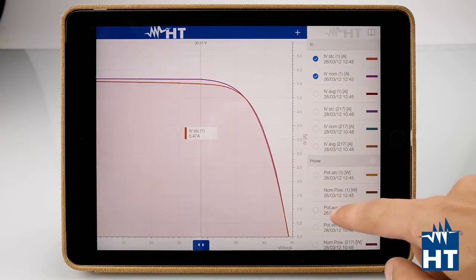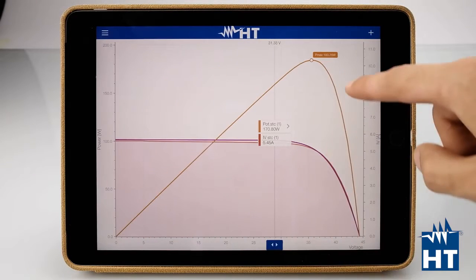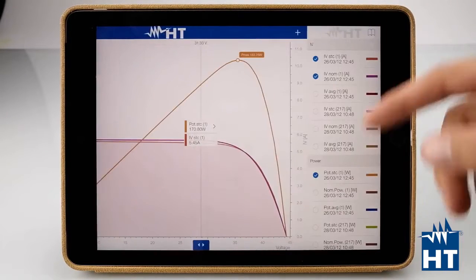Now I have two measurements on the same graph and I can compare also the power. So let's say, for example, power STC with the maximum power point here. And then you have the complete data to say something about, okay, this module is not okay, or maybe this string is not okay, or this plant needs more maintenance, or let's just clean the panels.